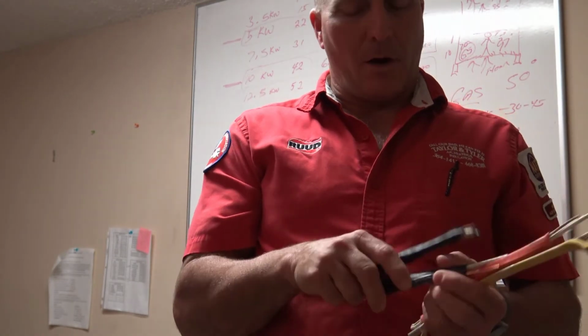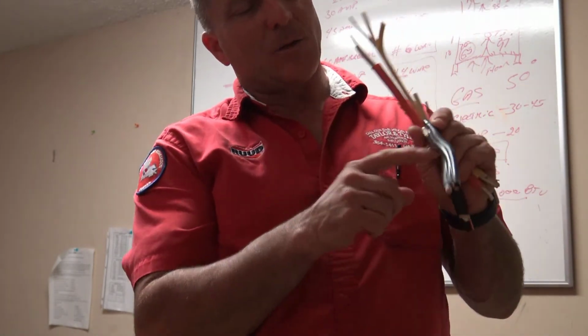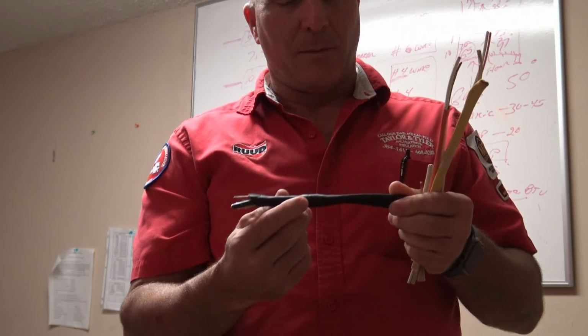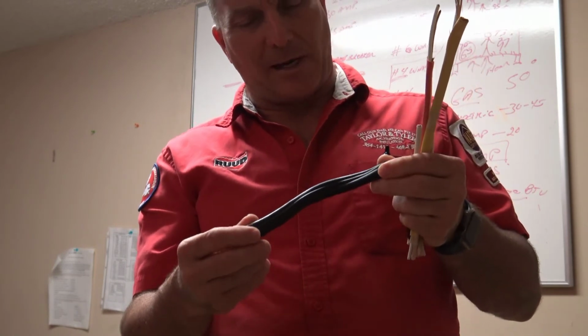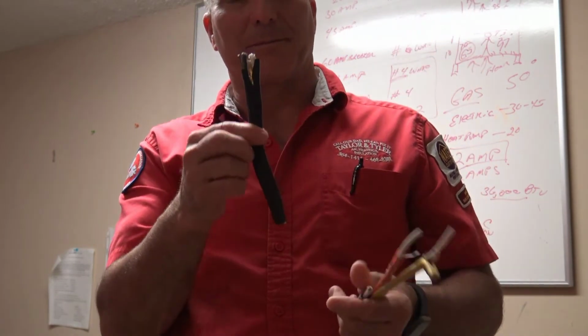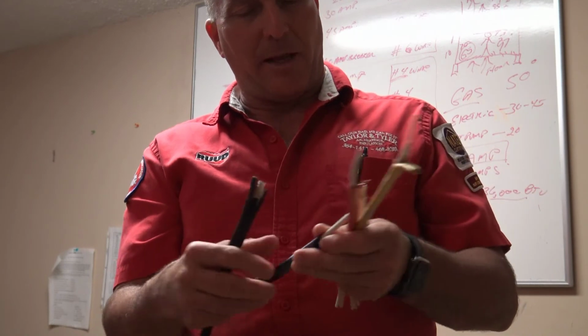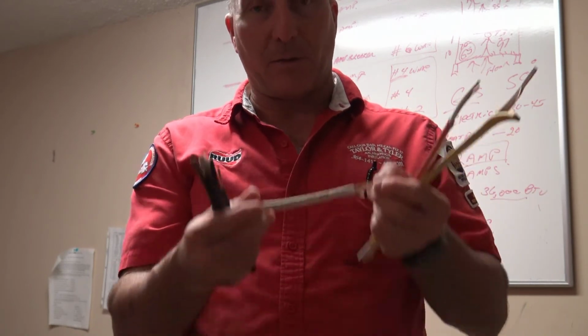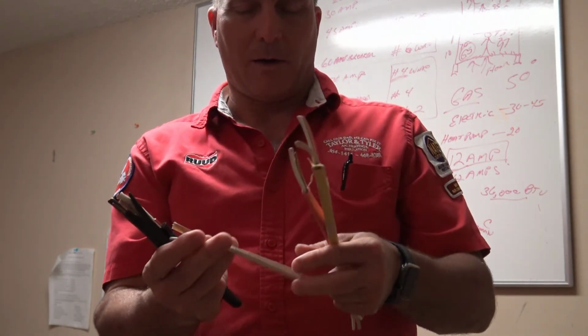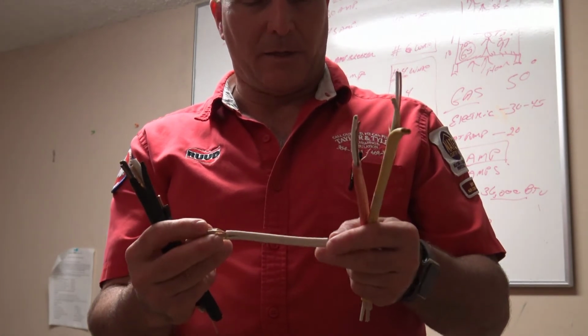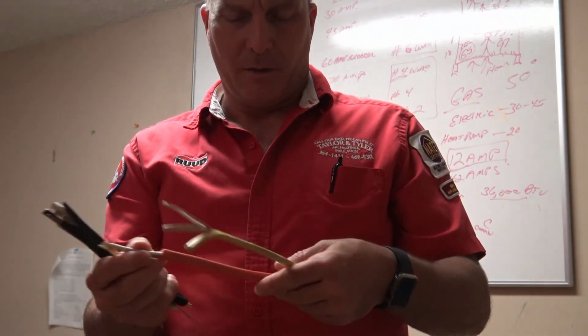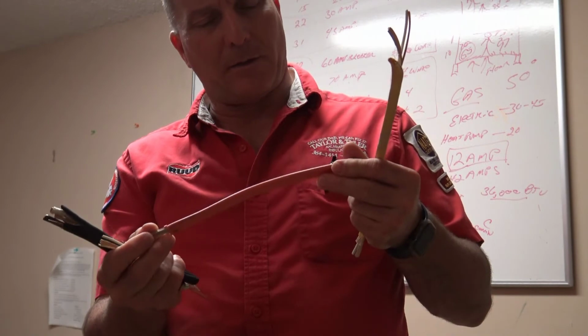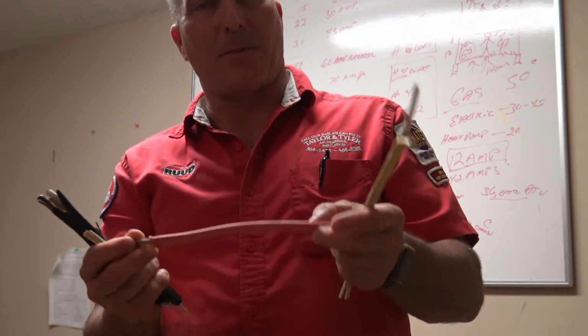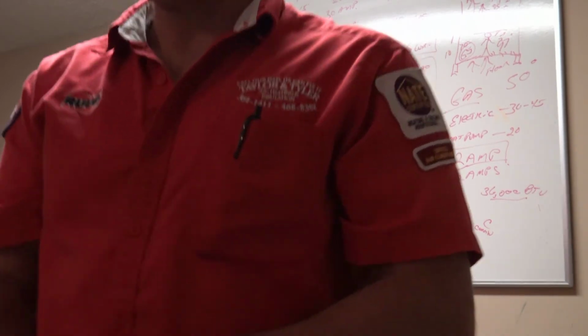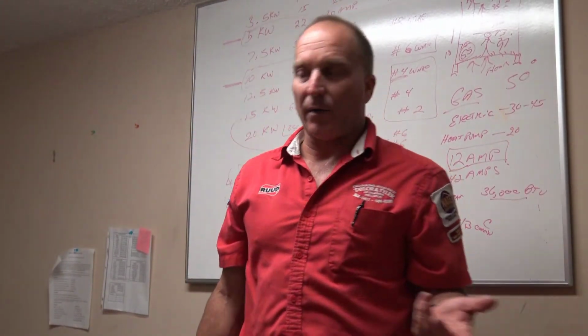But you can also read what size wire it is on here, but you actually have to find a piece of wire where it's actually written on, and this is not one of them, okay? So neither is the 8 wire. But it does have something written on the number 14 wire here, but it doesn't have it as a number 14. And 10 is written on here. They actually do have a number 10 on that one. So it is written on the wire, but if you have a long enough piece of that wire, you can actually read what size wire it is.